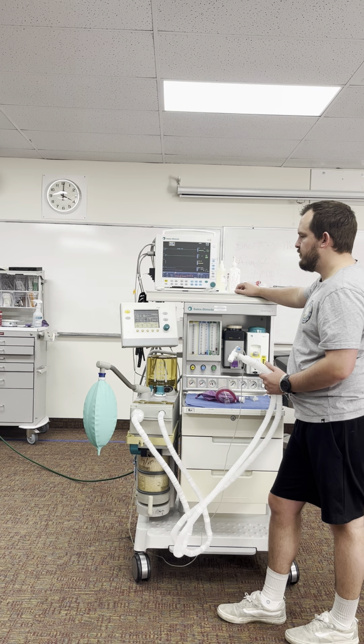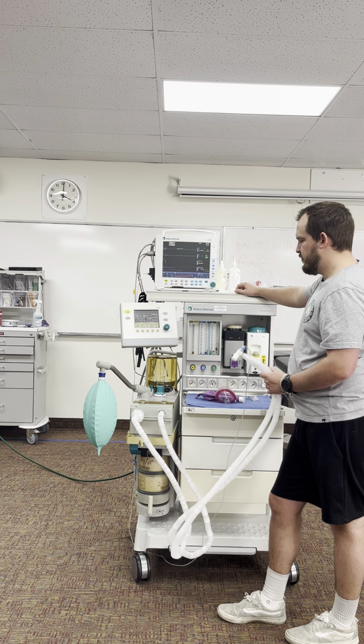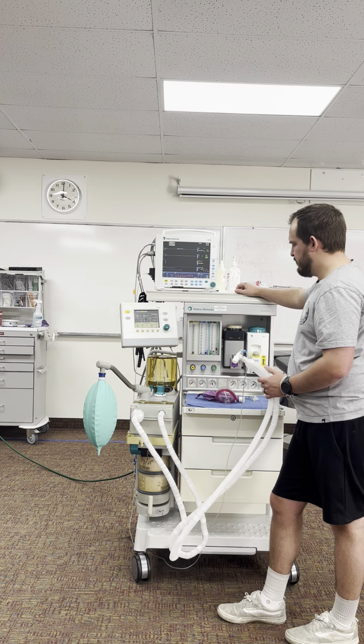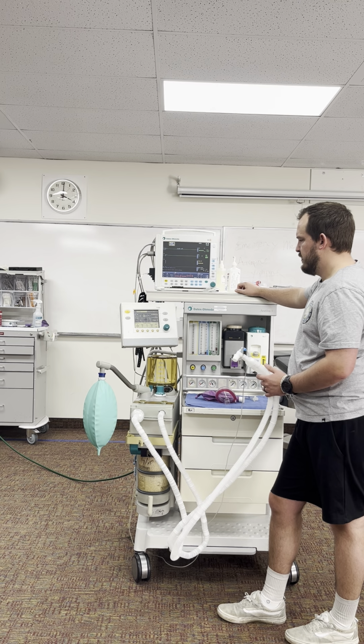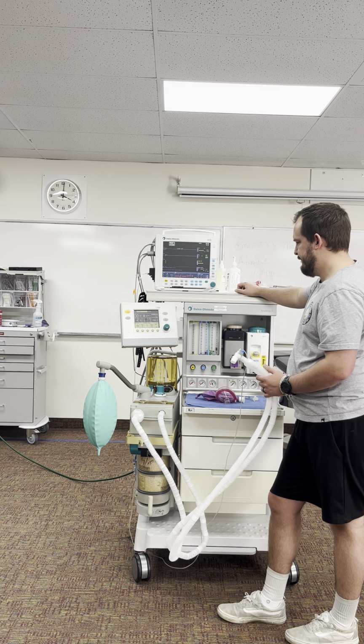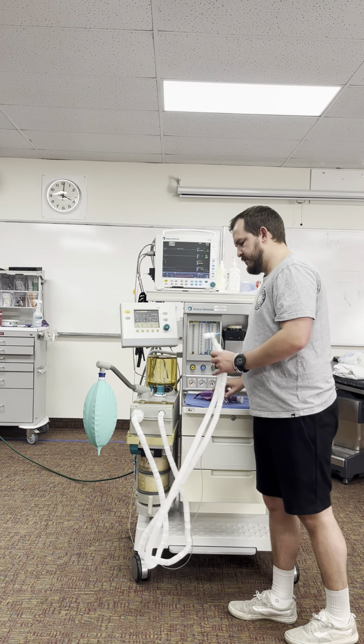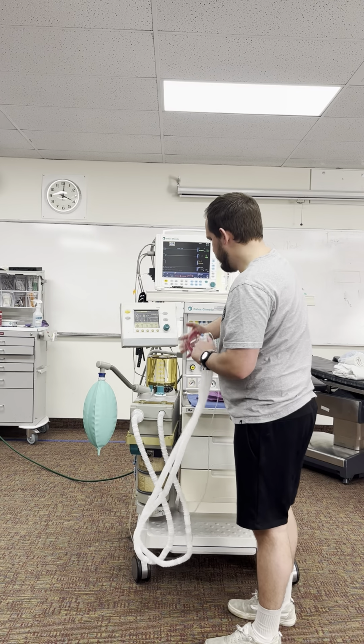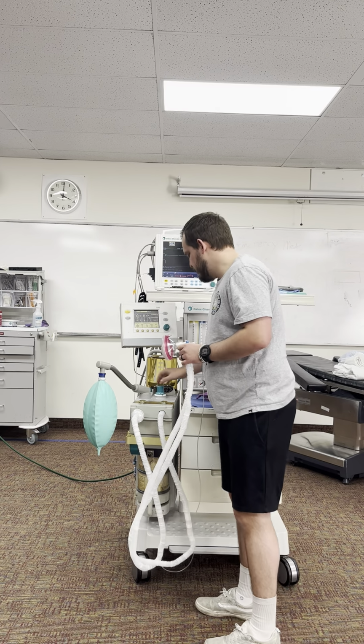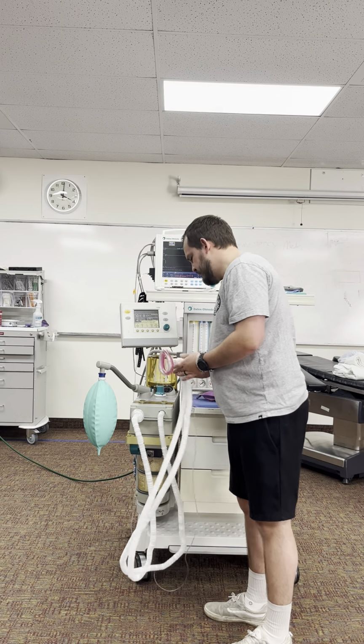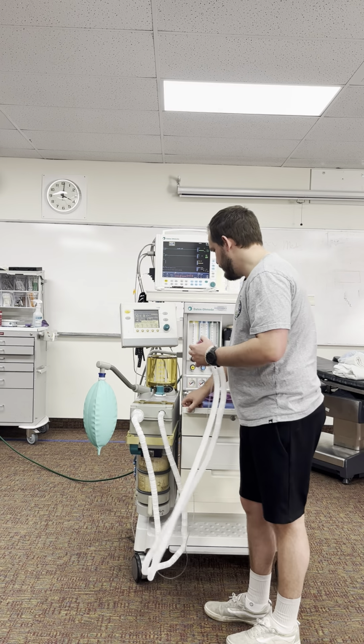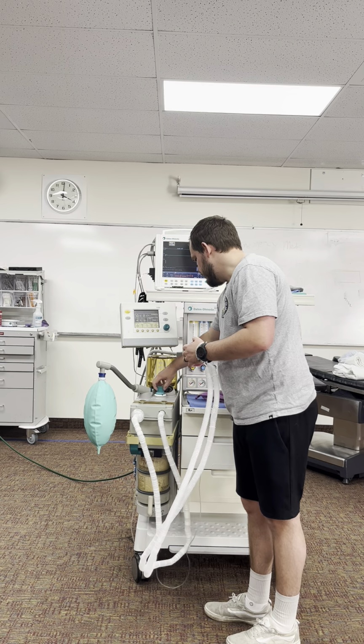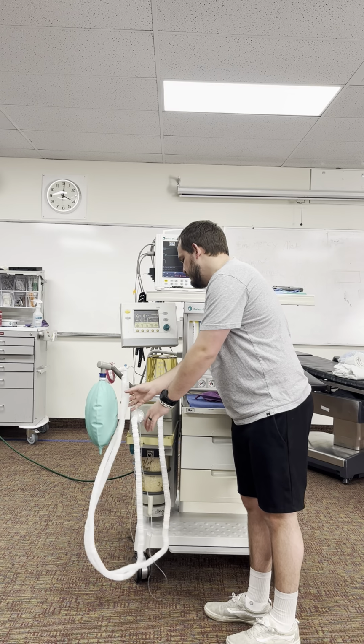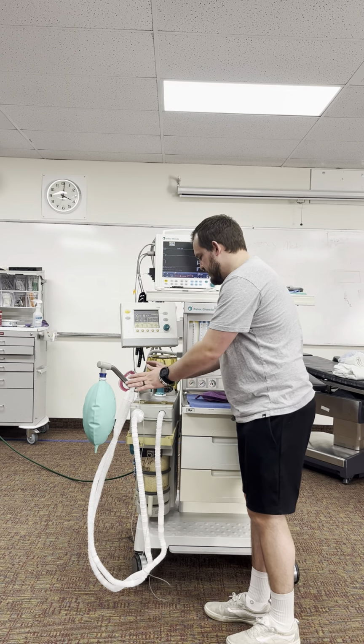Perfect, so now we're gonna get a low flow alarm, and then that will follow our disconnect alarm. So there's a low flow, and one more. Perfect, so that's our disconnect. So now I'm gonna just put my mask on because we're done with this. I'm gonna switch it back over to valve, and I'm going to increase my APL just to get my bellows. Bellows are good. I'm gonna leave that, so it's good and ready, everything's connected.